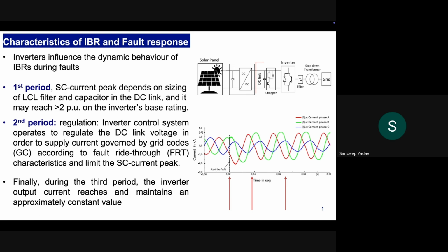Characteristic of fault response in case of inverter-based resource, we talked about it. The first period is the first arrow. If you see, this is the point when the fault has taken place, where the fault has been detected. For a few cycles, the short circuit current will depend on the sizing of the LCL filter and the DC link, the size of the capacitor in the DC link, how much current it can feed. So it can go up to, say, 2 per unit, depending upon the inverter rating.